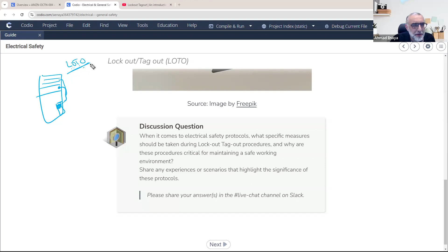In a factory, LOTO is more relevant because devices are connected directly. In a data center, servers are connected by power cables to a distribution panel, so we have full control and can disconnect the electricity or unplug the cable. In many cases, LOTO isn't applicable in a data center since equipment is controlled by visible power cords we can disconnect. But in factories, or when dealing with heavy electrical components, you may need to follow LOTO. For servers or switches, it's different since we can simply unplug the power cord. So it's not always applicable; in some cases there are easier ways to achieve the same objective.